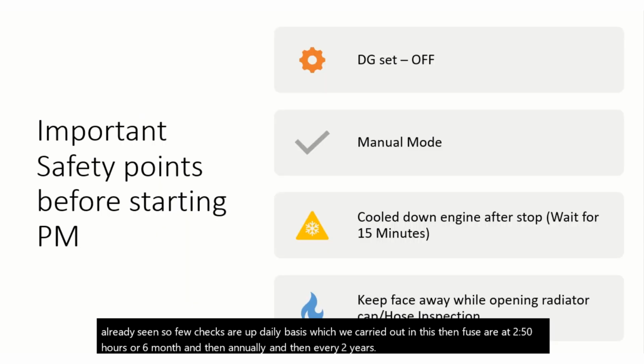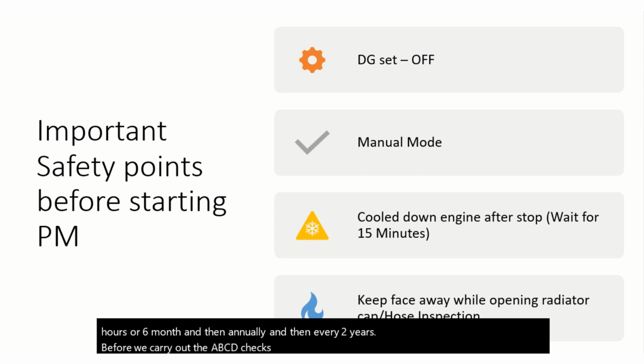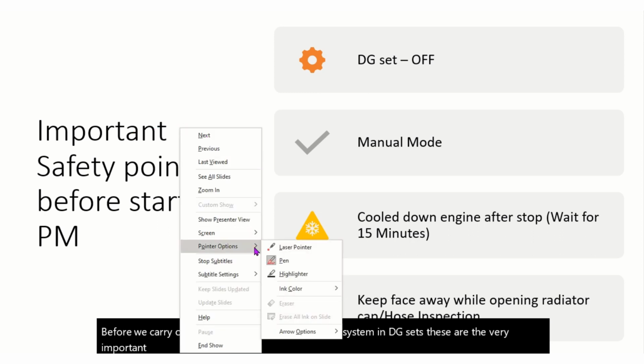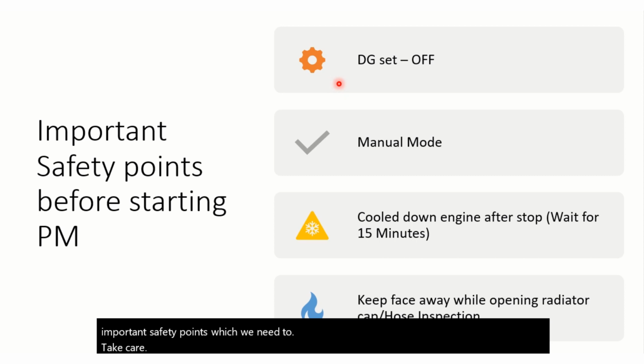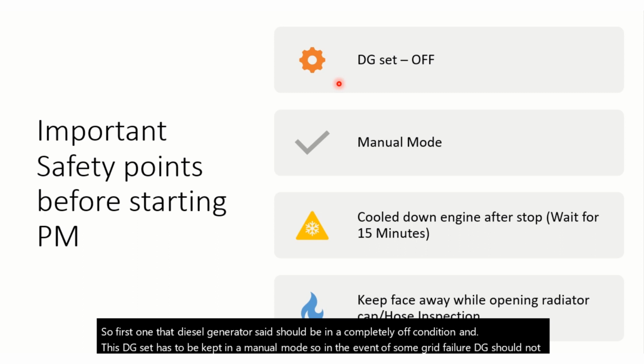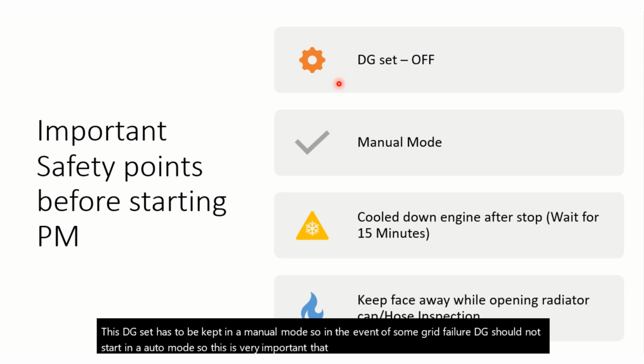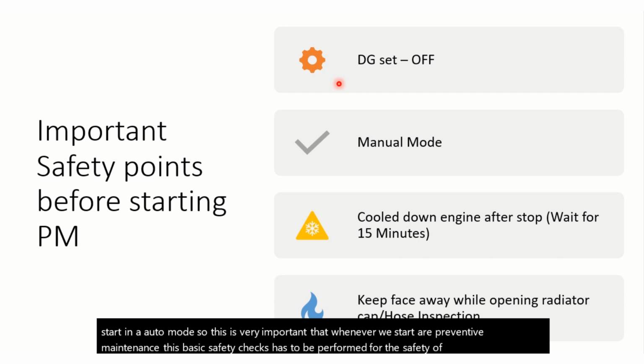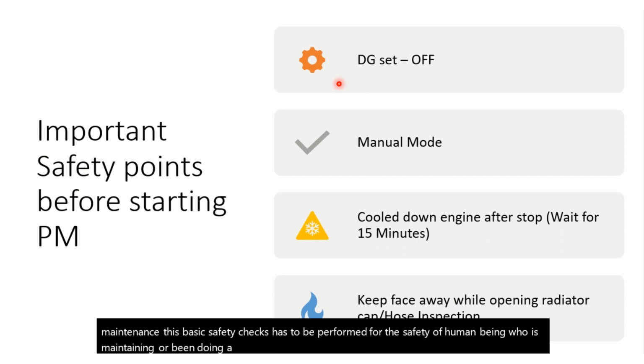Before we carry out the ABCD checks of any cooling system in DG sets, these are the very important safety points which we need to take care of. First, the diesel generator set should be in a completely off condition, and this DG set has to be kept in manual mode. So in the event of some grid failure, the DG should not start in auto mode. This is very important, that whenever we start our preventive maintenance, these basic safety checks have to be performed for the safety of the human being who is doing the maintenance on the DG set, as well as for the equipment. Third one is the DG has to cool down.